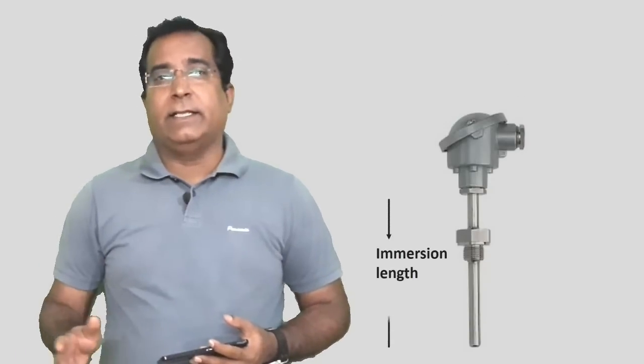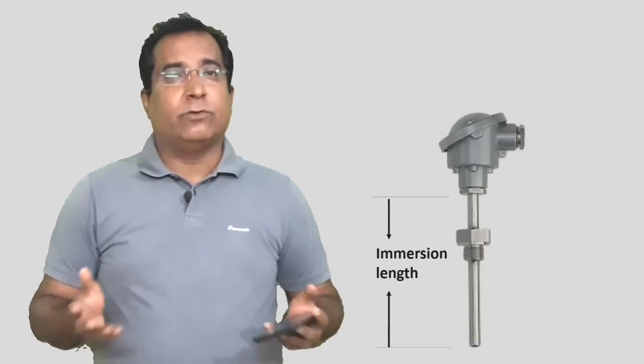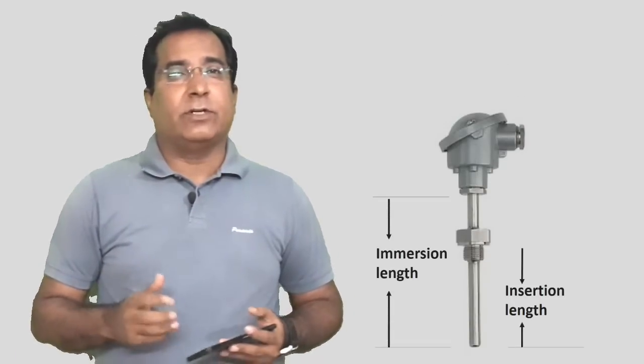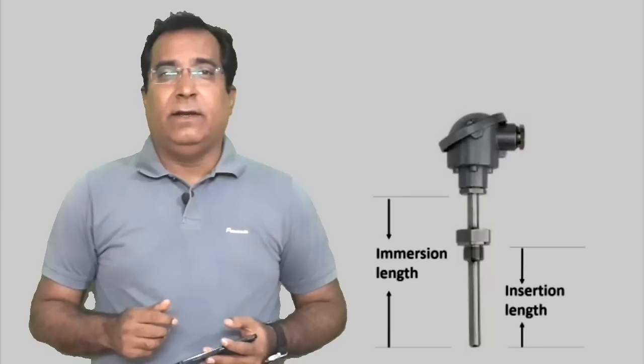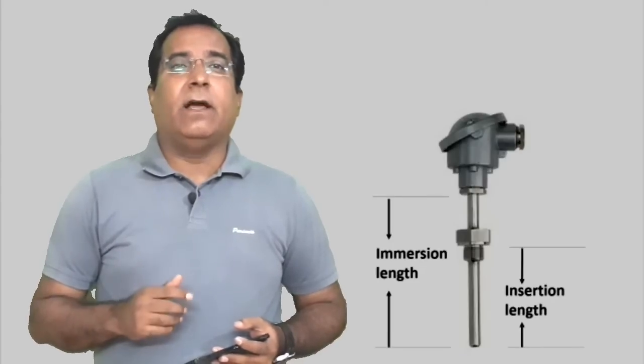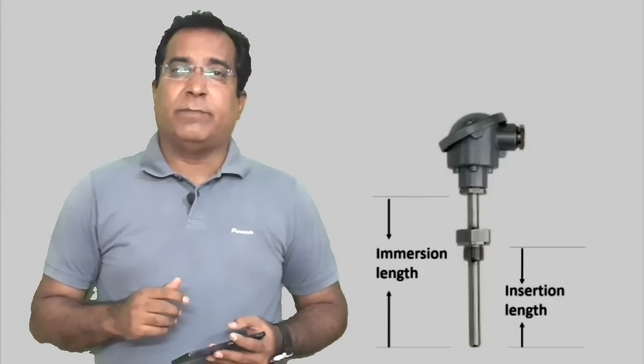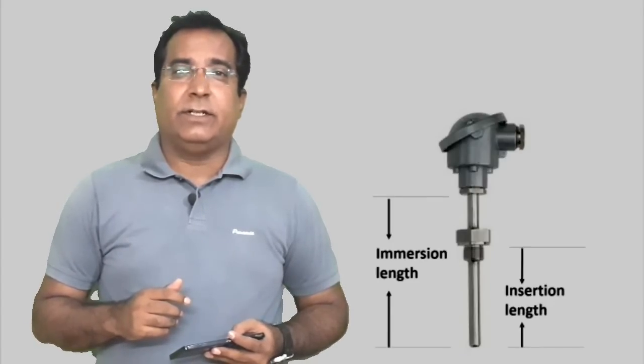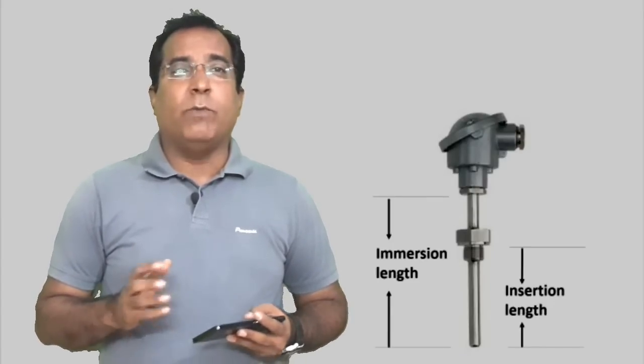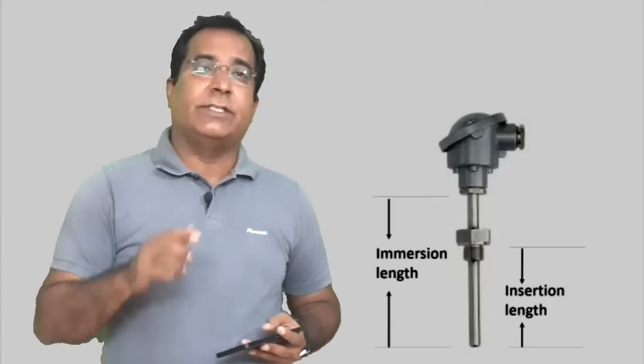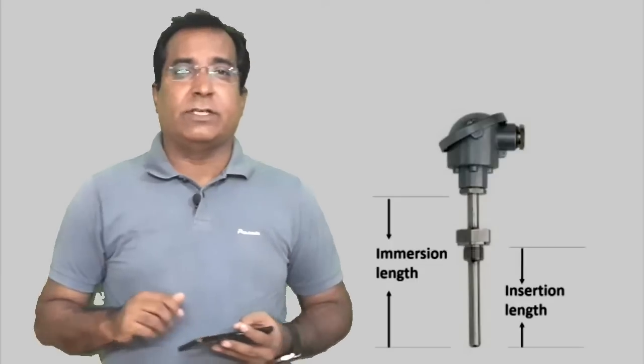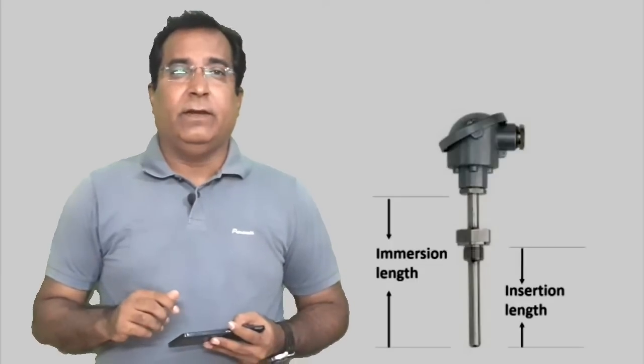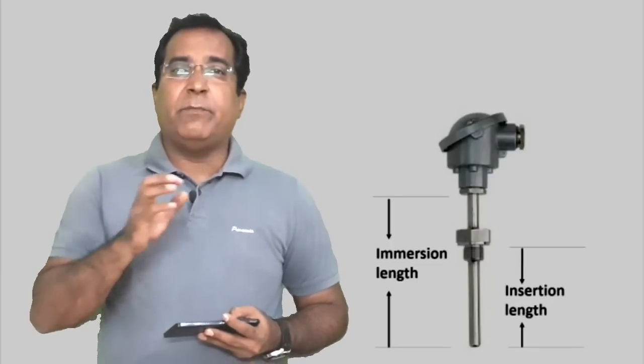RTD or thermocouple is specified for immersion length whenever you purchase. It is length from thread of the terminal head to the tip. Second length that is insertion length is important to consider. This is very important parameter in sensors installation. This means how much the sensor is inserted into the process connection.